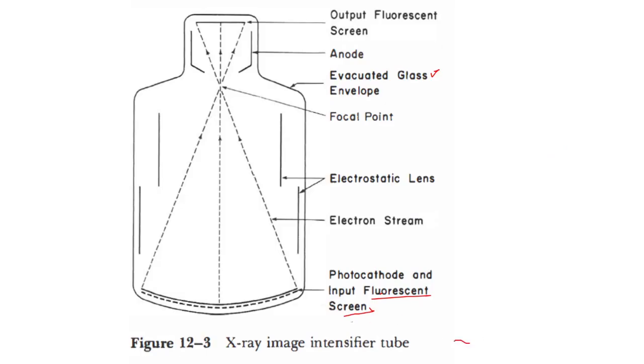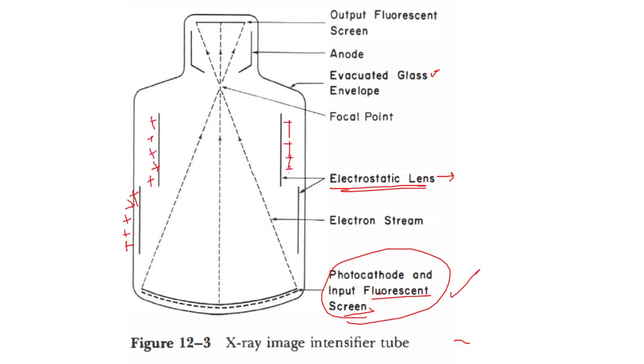Now let us learn about the electrostatic focusing lenses. These are made up of a series of positively charged electrodes plated onto the inner surface of the glass envelope. Their main function is to focus the electron beam as it flows from the photocathode to the output phosphor fluorescent screen.